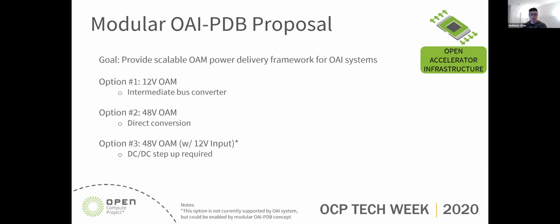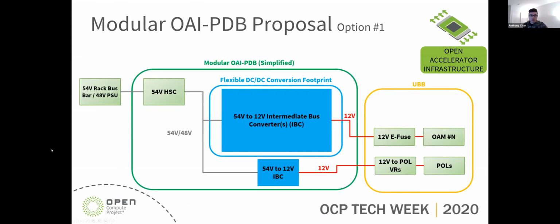Option three is interesting because it's currently not enabled by the OAI specification, but we do see an opportunity where we can enable people to use 48 volt OAMs, although their data center infrastructure or rack topology is still on a 12 volt solution. So we also want to look into the opportunity of enabling a step up solution. In the following slide, let's go over a little more detail.